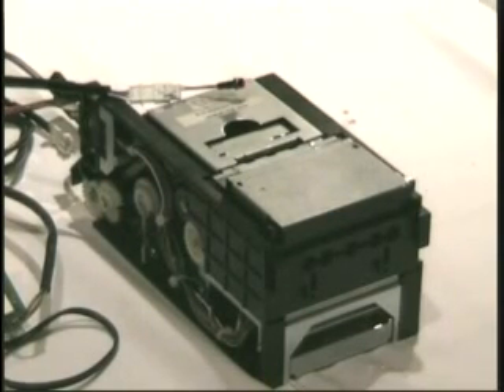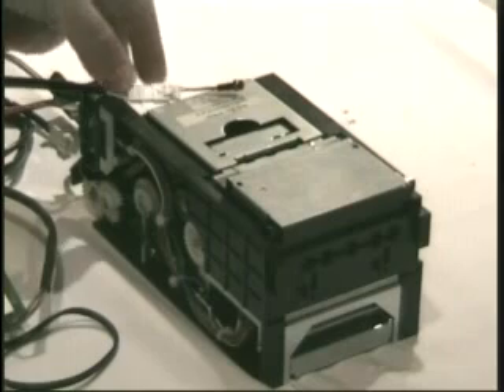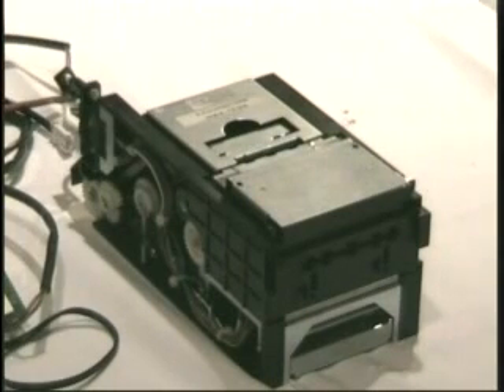So cleaning and calibration, that's the best way to keep a validator up. Cleaning, whenever it gets dirty. If you're going to start up a PM program, you want to take a look at them at least once every 6 months. Trying to get your boss to start that I know is next to impossible. But calibration, if it needs it, like I said, at a minimum I try and do it once every 6 to 9 months, just to be on the safe side.